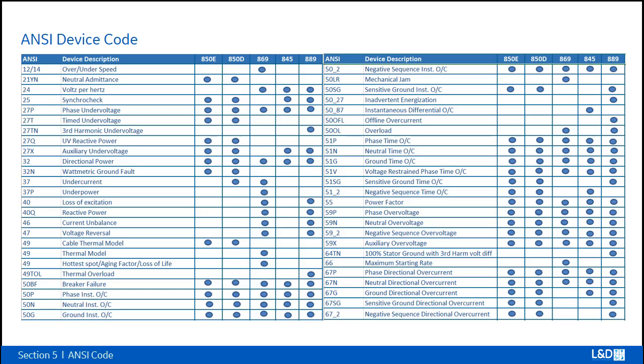And other relays have their own special functions, like 845. It has the 87T instantaneous differential. 889 also has the 50/27 inadvertent energization. Sometimes it's called accidental energization. Motor also has the 66 maximum starting rate. So that is the table. We can see the common platform and the specific elements for each relay.